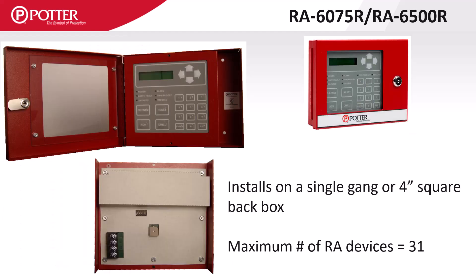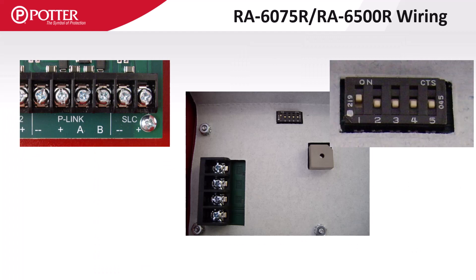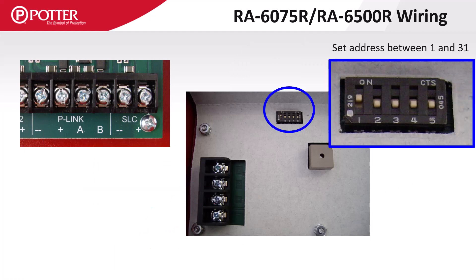Potter remote annunciators come with a lockable hinged door and have several back box mounting options. The P-Link circuit connects to the annunciator's positive, negative, A and B terminals, and it needs to have a P-Link address assigned before connecting power.